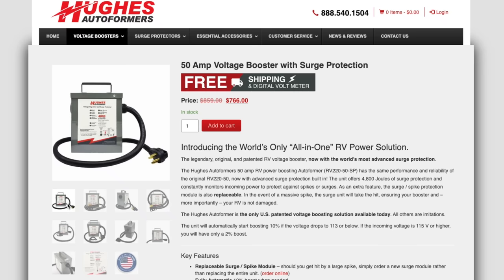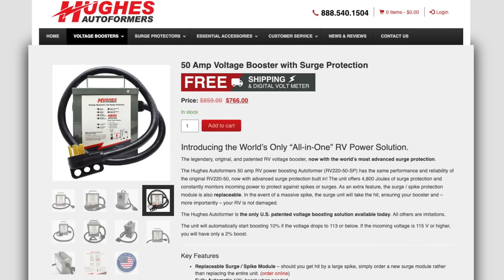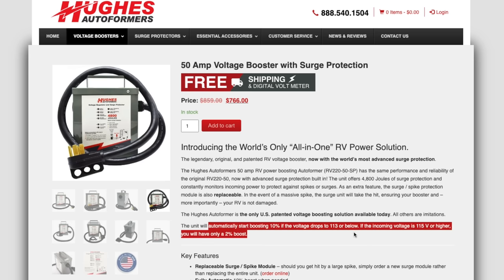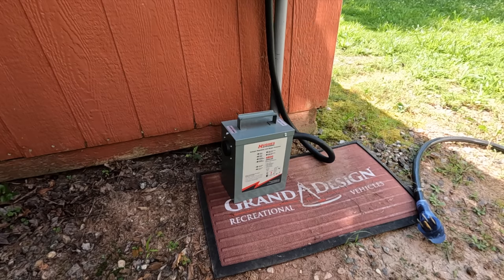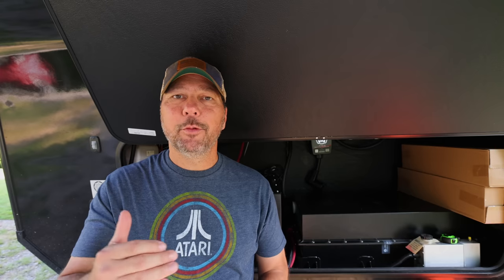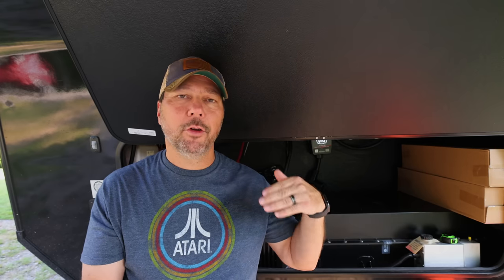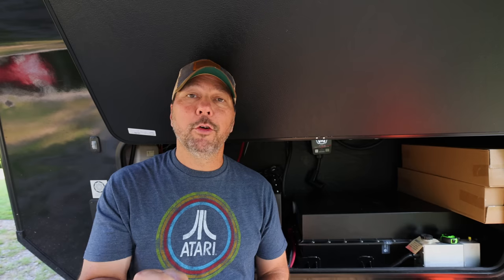So what is an autoformer? Full video on this that I'll reference below, but the long and short is: remember that low voltage I talked about where the EMS will just cut it off? An autoformer takes it a step further and tries to boost your voltage. It runs in line with your power, just like the surge suppressor would — you typically put it in line before the surge suppressor. The Hughes autoformer will bump up 2% all the time, but if you go below 113 volts, it'll boost 10%.